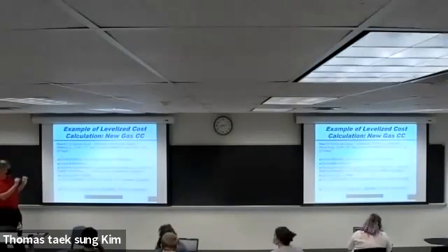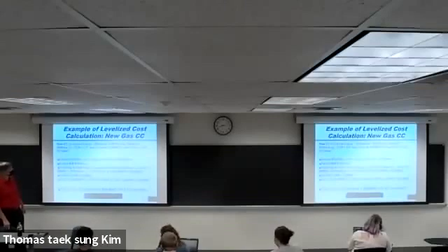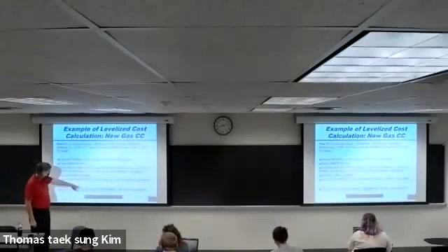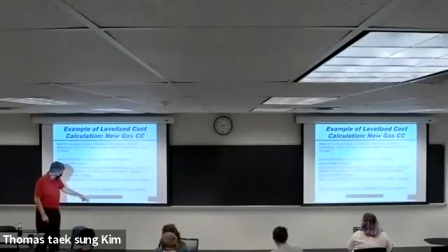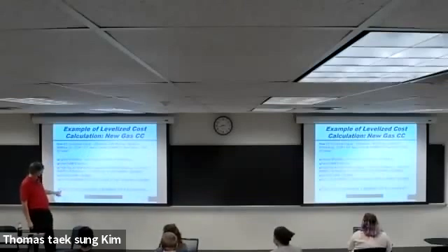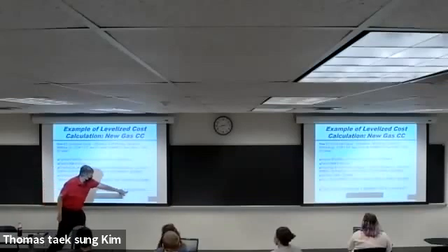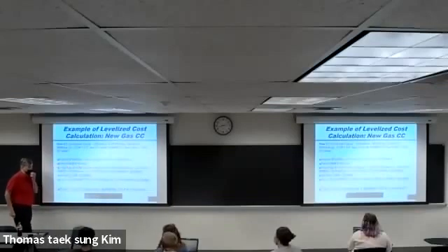But if you walk through all that math, you'll get 21. So the total cost of electricity in this example, assuming that the gas price is really $3 instead of $4, which I obviously forgot to change, at any rate, is $48 or 4.8 cents per kilowatt hour.